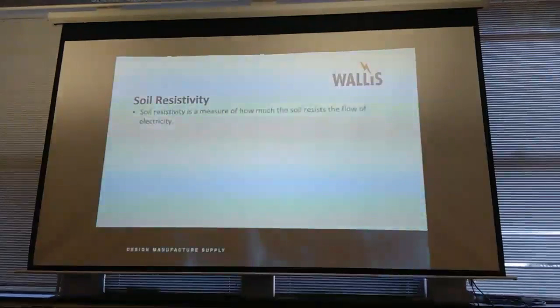Right, forgive me. So, as I say, it was bouncing around a little bit. Soil resistivity is a measure of how much the soil resists the flow of current. So again, the different geologies across the country, across the county, across the planet, will resist the flow of electricity to a greater or lesser extent. You need to know what that is before you can start putting your earth rods in the ground, your tape in the ground. All the earth rods, all the tape, is a means to an end. It's a means of connecting your high voltage earth, your LV system, to the general mass of earth. We could get a wire and just go like that, it's dead easy. But it's just a means to an end.